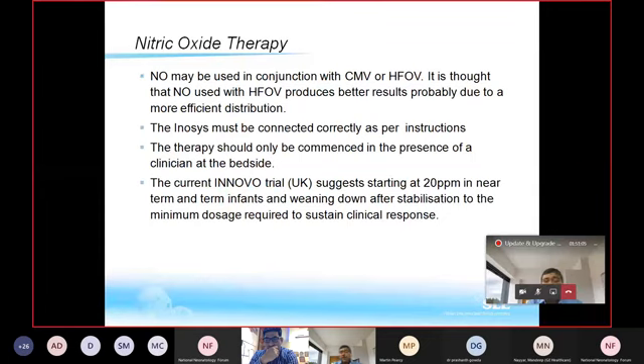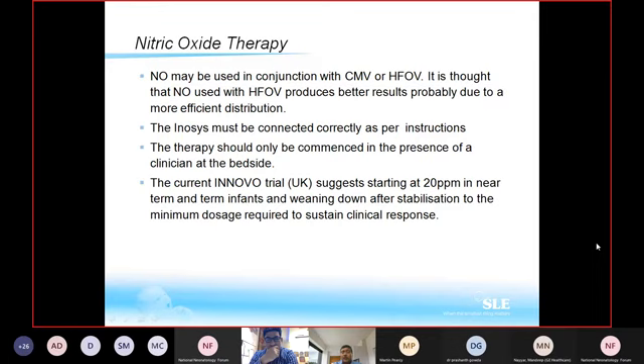As you know, when this gas mixes with oxygen, it creates NO2, which is very toxic. So it is diluted in nitrogen when it's being given. But at the same time, you also need to ensure that there is a sufficient distance between where you add this gas in the connection, which I will show, and the ET tube. Approximately 20 to 25 centimeters should be there, so that it gets sufficient time to mix before it reaches the patient. This is another thing that you need to ensure while you are adding this.